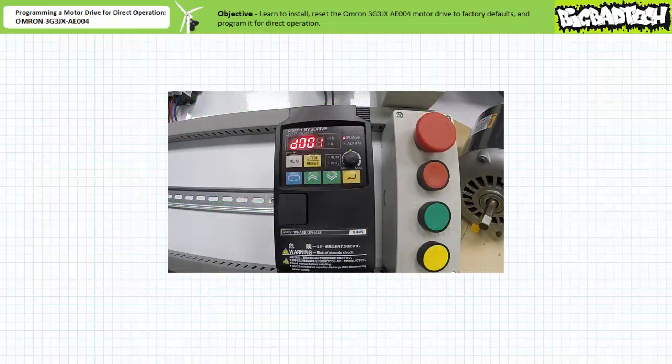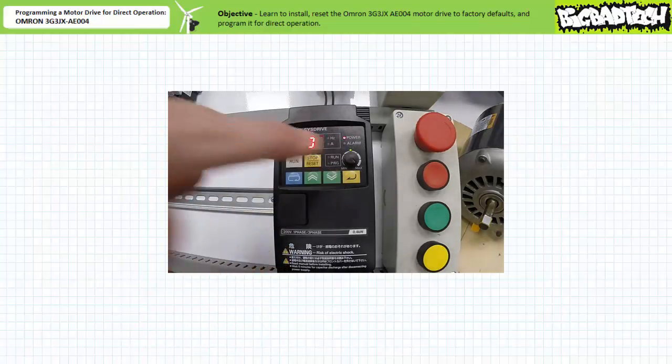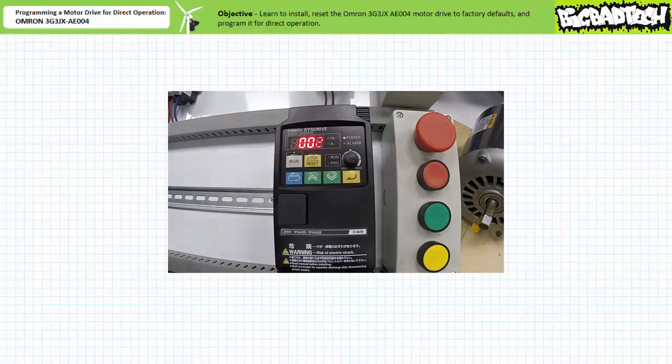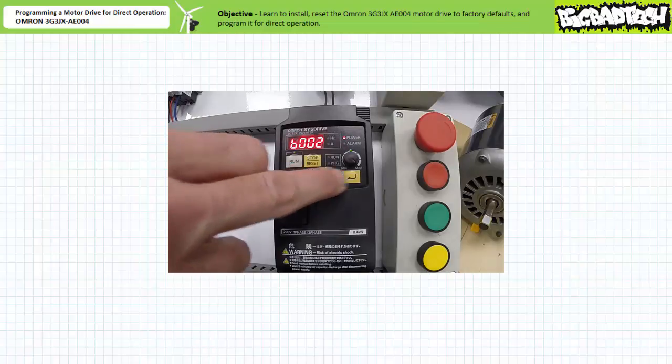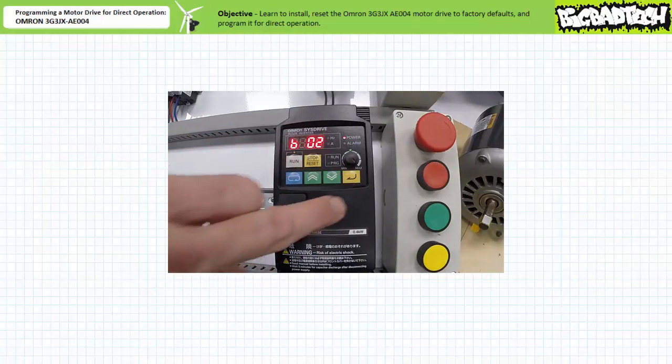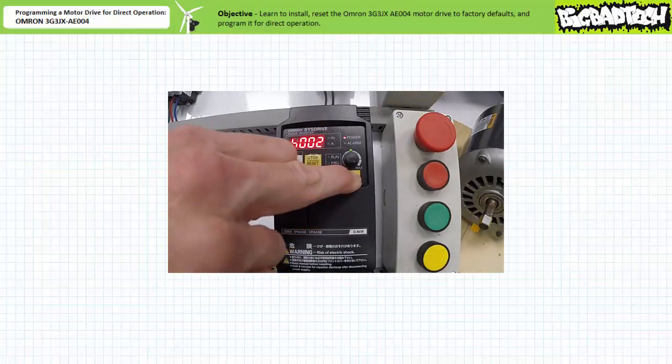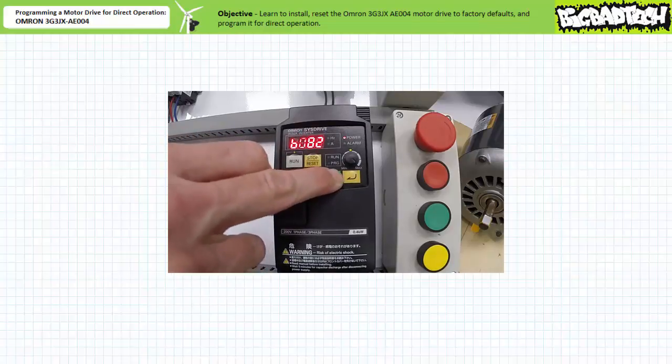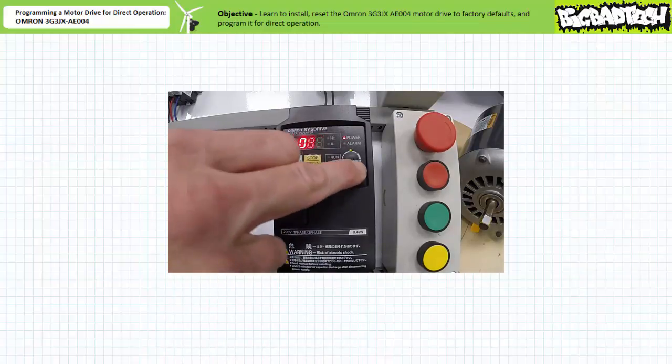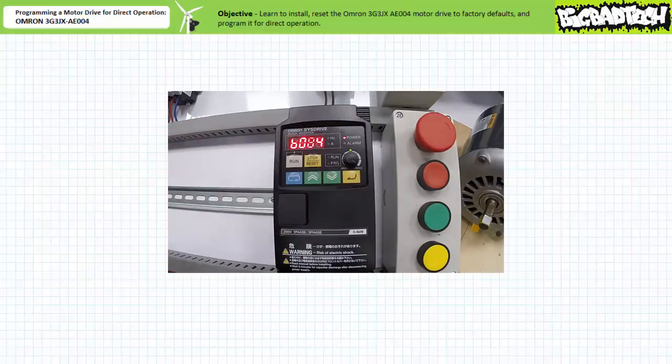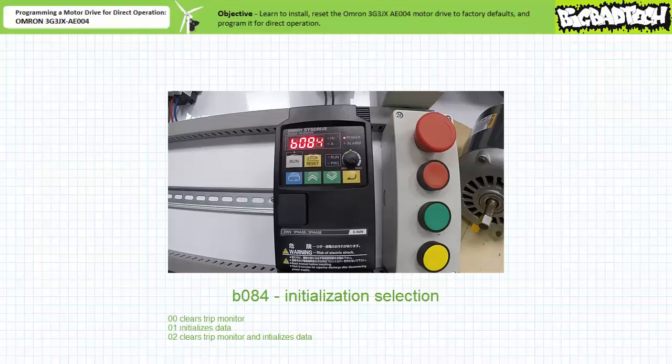Starting in D001 mode, I simultaneously press increment and decrement. The first digit blinks. I increment or decrement to B, then press enter. The second digit blinks. I increment or decrement to zero, then press enter. The third digit blinks. I increment or decrement to eight, then press enter. The fourth and final digit blinks. I increment or decrement to four, then press enter. Once the display stops blinking, I'm in parameter B084.